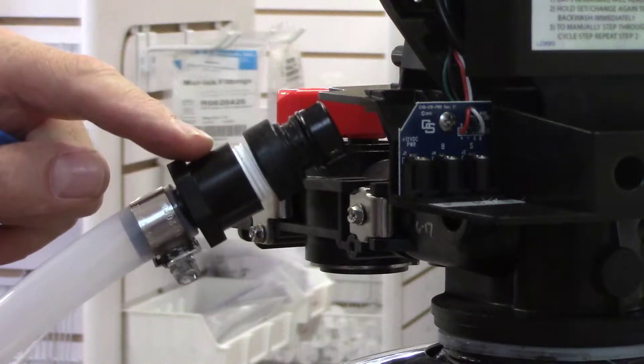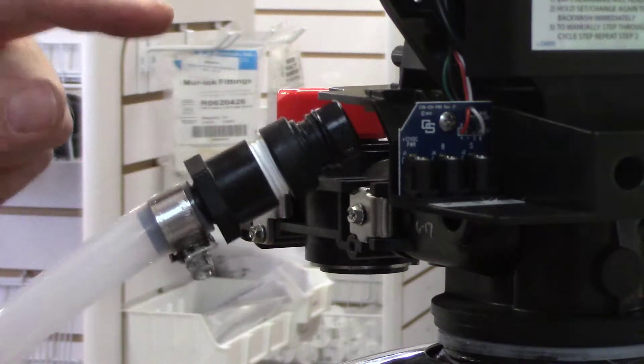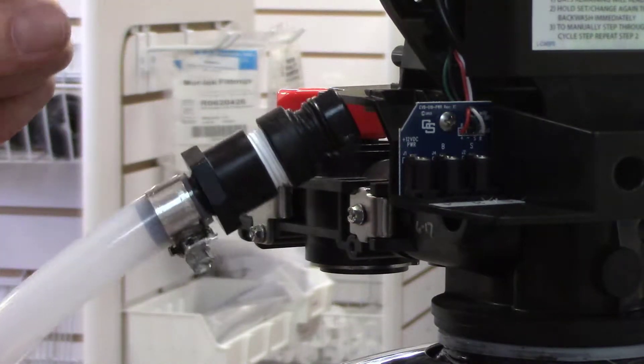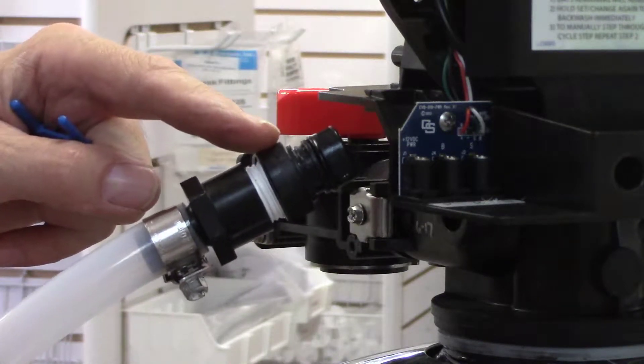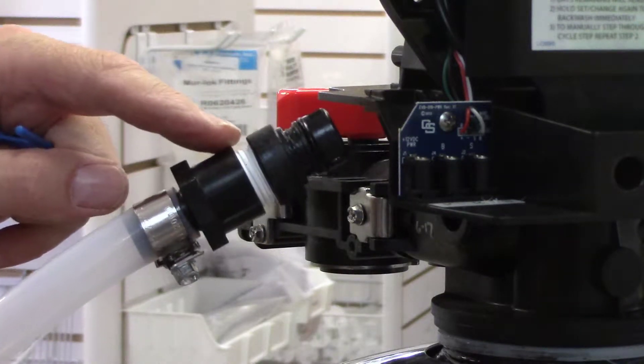This is the flow control housing and this is the half inch female by five-eighths male barb fitting. You're going to screw the barb fitting onto the drain line flow control housing. Apply tape and paste, not too much, and don't overtighten it or the fitting will crack.